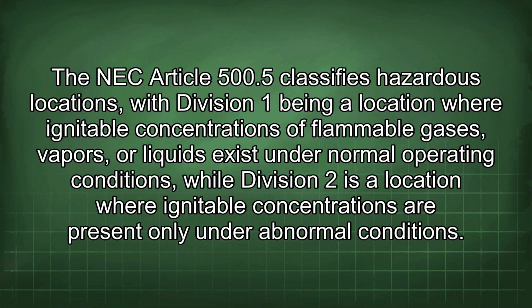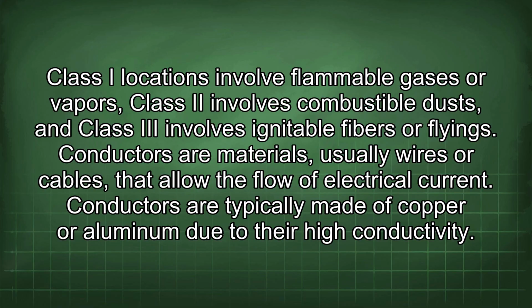The NEC Article 500.5 classifies hazardous locations, with Division 1 being a location where ignitable concentrations of flammable gases, vapors, or liquids exist under normal operating conditions, while Division 2 is a location where ignitable concentrations are present only under abnormal conditions. Class I locations involve flammable gases or vapors, Class II involves combustible dust, and Class III involves ignitable fibers or flyings.